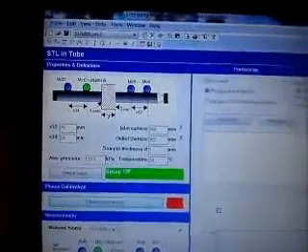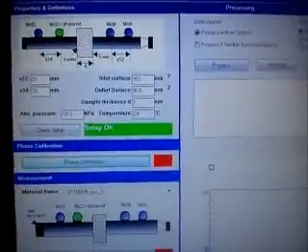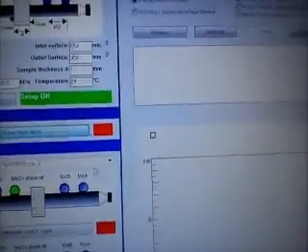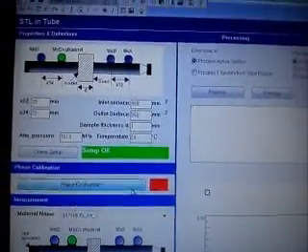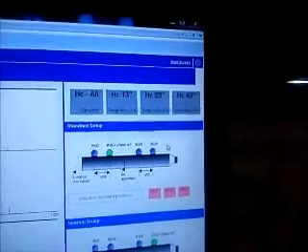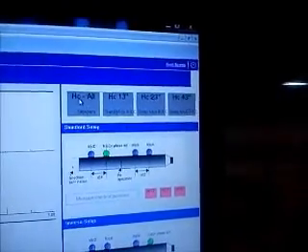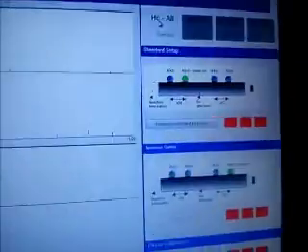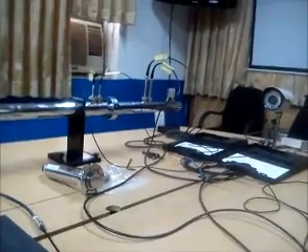Going back to STL in tube, setup is okay. Phase calibration, HC all. HC all is by default the position of 1, 2, 3 and 4, A, B, C, D, all 4 microphones. This is known as HC all and we are calibrating it, so measuring the standard position.